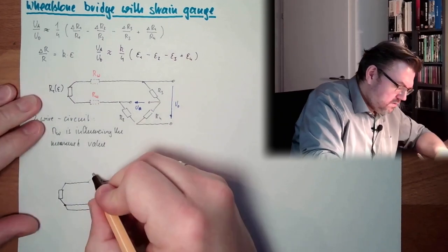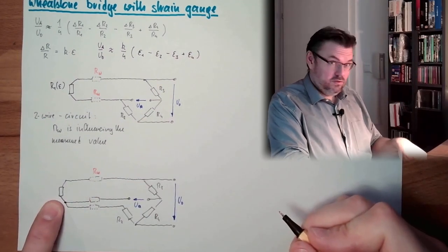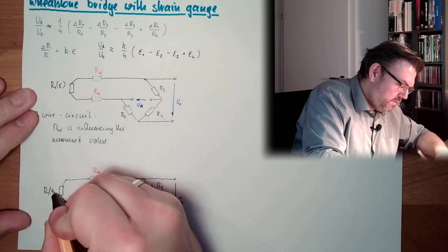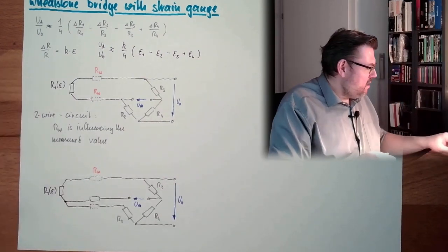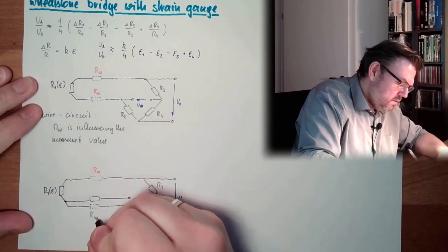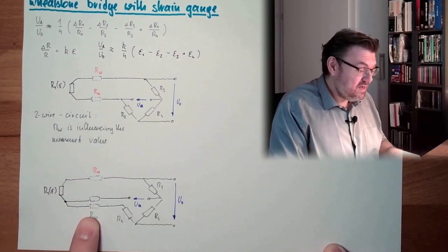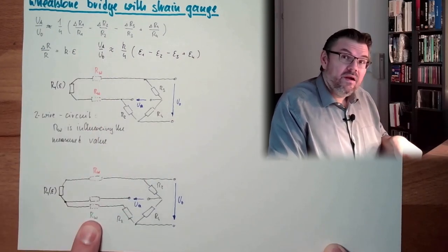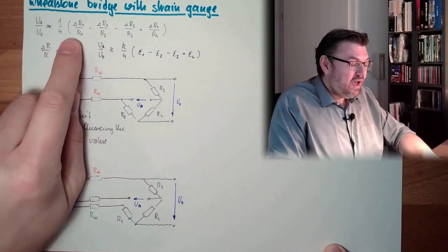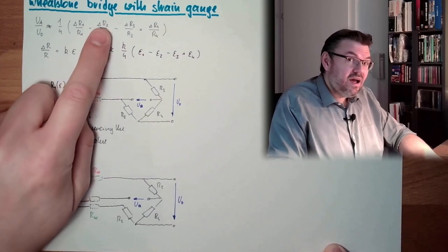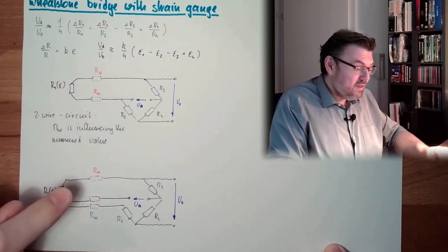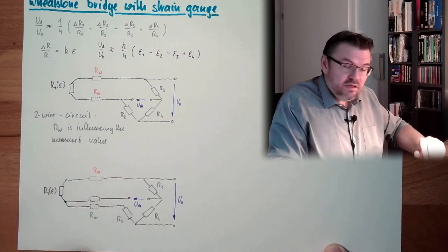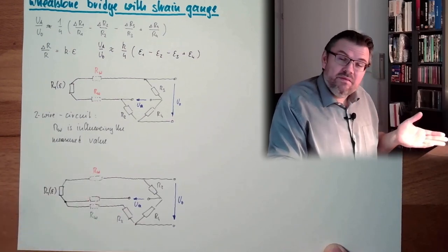Here I have wire resistance. This is R1 again, a function of epsilon — the strain gauge. Here we also have a wire. However, this wire resistance is already in the branch of R2, and the branch of R2 is negative. So if this wire and this wire are the same length, these virtual changes compensate each other — one is in the R1 branch and one is in the R2 branch, compensating perfectly.